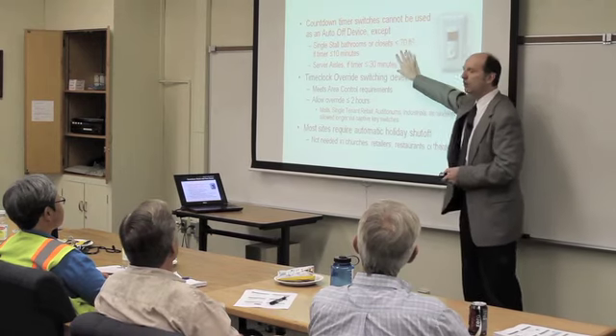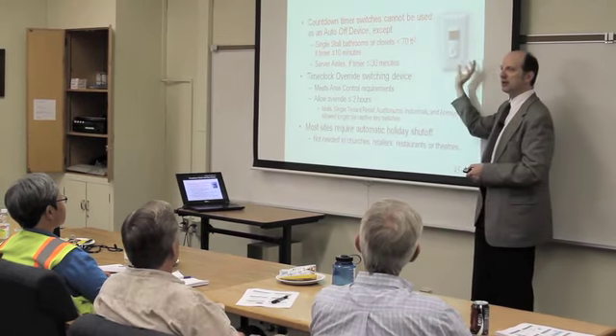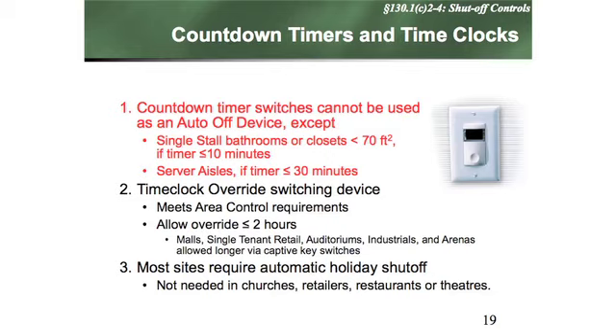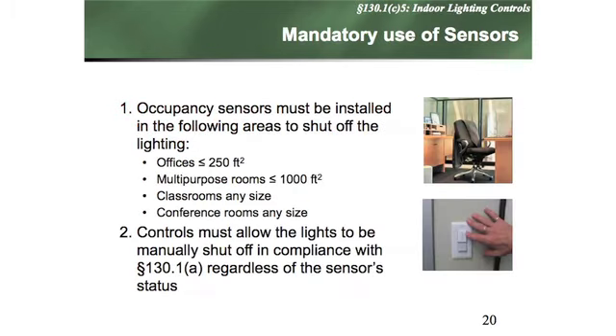But those are the only two places inside buildings that you can use timer switches from now on. The time clock hasn't changed at all. Still, make sure that it goes on at a certain time and goes off at a certain time. If somebody overrides after hours, it's on for no more than 2 hours, except for certain buildings. These are the buildings where, in the last code go-around, they said specifically, okay, we know we told you you could use anything you wanted to turn off the lights. In these 4 spaces, though, it's got to be an occupancy sensor.